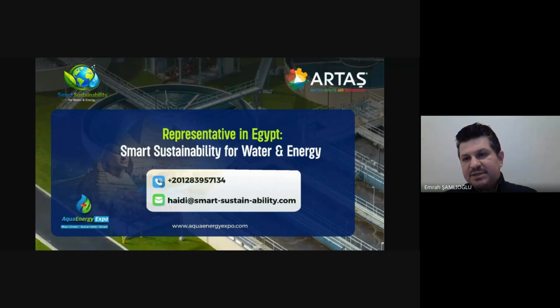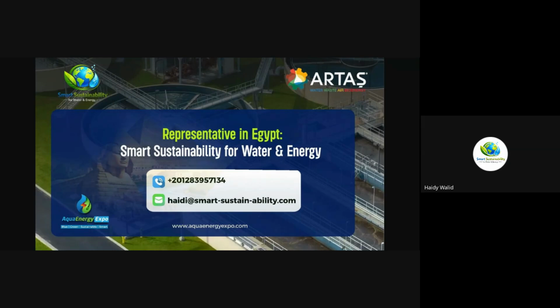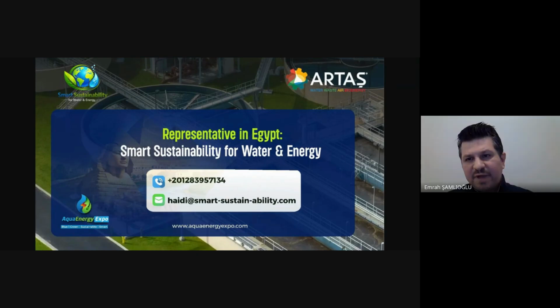Actually it depends on the requested outlet water quality, but normally for fresh water they can use standard brackish water membranes. There are some good membranes from Toray and DuPont, and also high rejection membranes available. There are some criteria for membrane selection: what is the raw water quality and what is the requested treated water quality - we choose membranes according to these main topics. It's water from wells and city water. For well water, they can generally use brackish water reverse osmosis membranes.